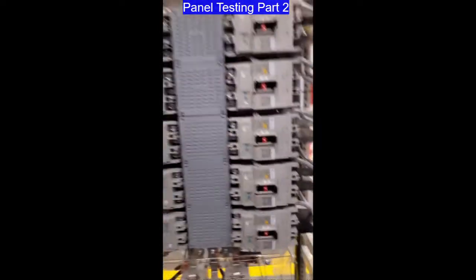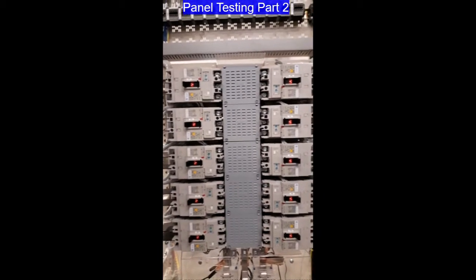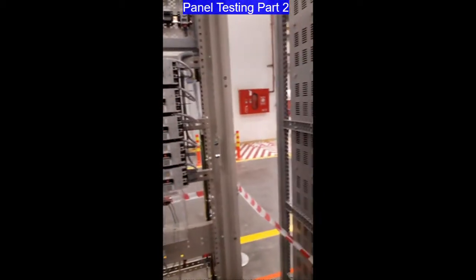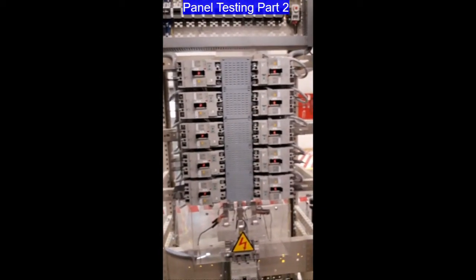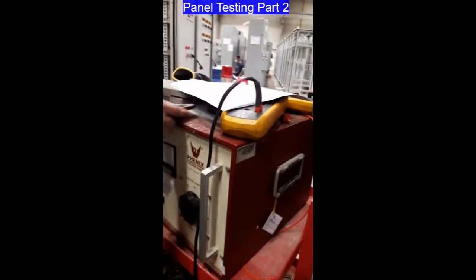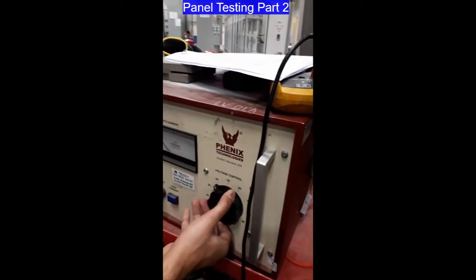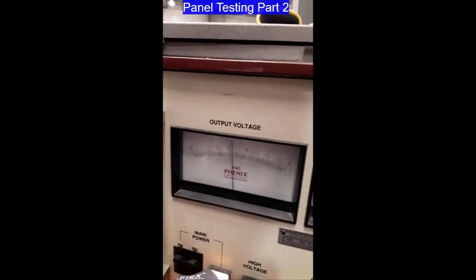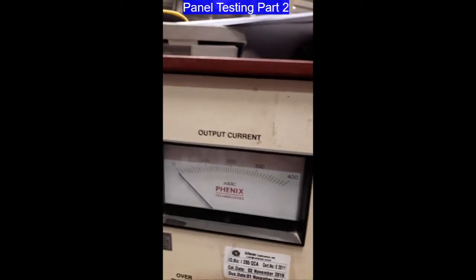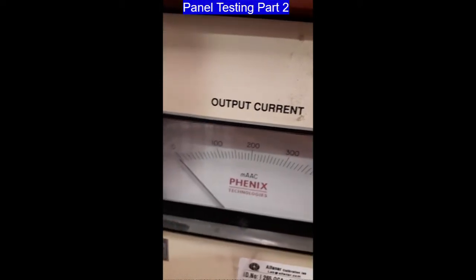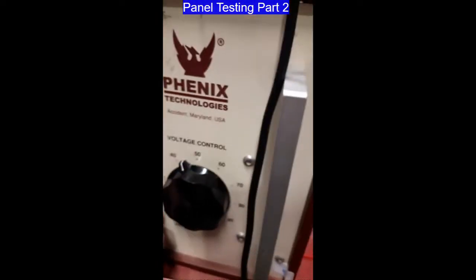Here we're going to switch on all our breakers. All breakers on. All right, we're going to do the high voltage now. I'm going to check now, and here we're going to inject 2.2 kV for 60 seconds. This is the output voltage and this is the output current. In case there's a problem in our panel, you will find movement in this output current. Time starts now.